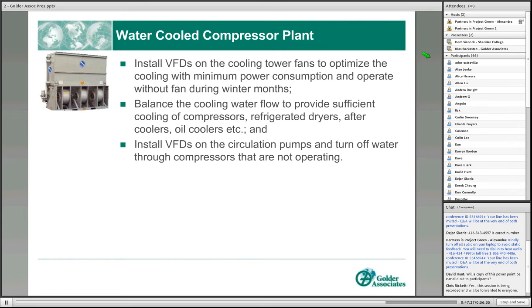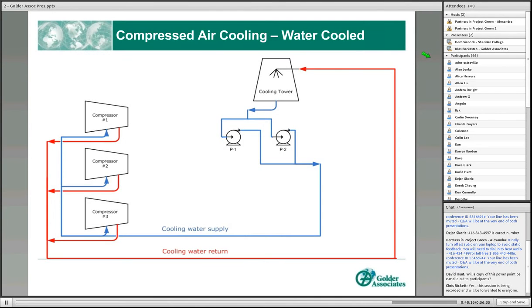Just a few words on the cooling system side of things. If the compressors are water-cooled, methods of making the water cooling more efficient can include installing a variable frequency drive on the cooling tower fans. That way, in the fall and the spring, you can slow down the fan and reduce the electricity used by the cooling tower fans. Other items are balancing the cooling water flow so that you get the proper flow to each individual compressor, and installing automatic shut-off valves so that when a compressor is not running, the water flow to it is turned off. No point cooling anything that's not requiring cooling.